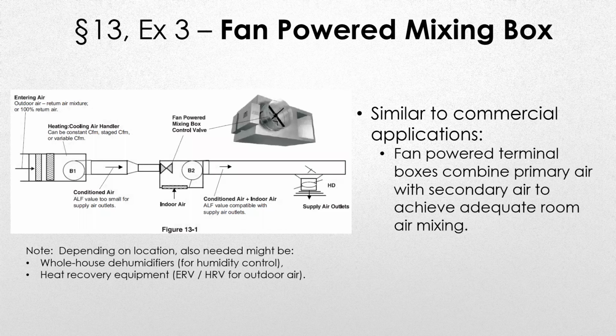So those of you that have done schools or hospitals or some commercial work, you're all familiar with a fan-powered mixing box. Basically, we're showing here that we have a heating and cooling air handler, and it may be putting out 400 CFM per se. And then it has a second fan-powered mixing box that sucks in additional return air or indoor air and mixes it with the other air and then distributes it out to the rest of the home.